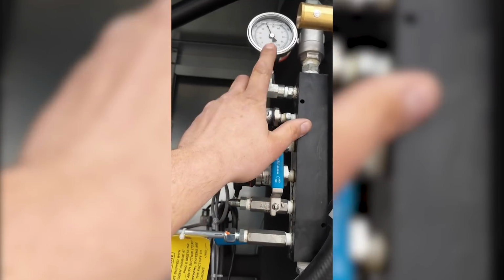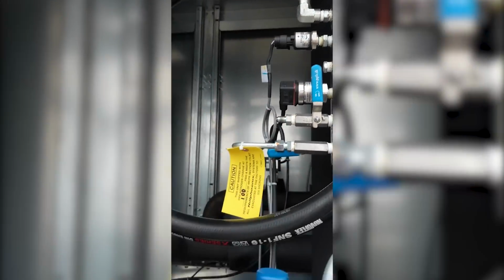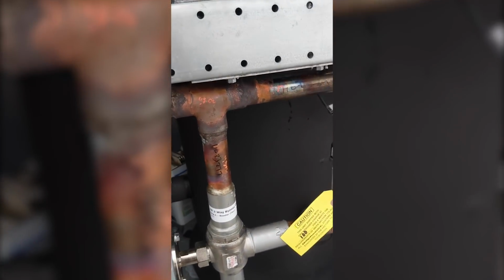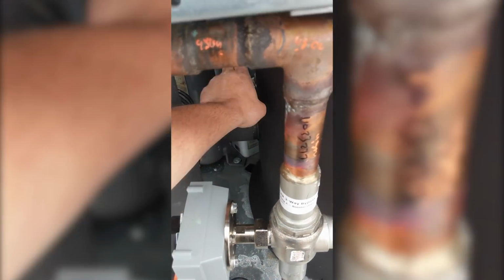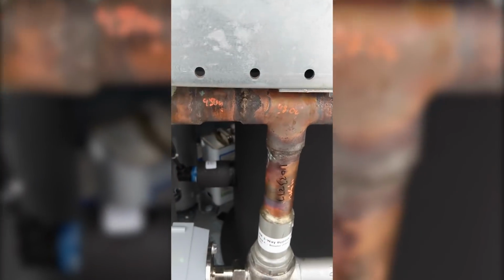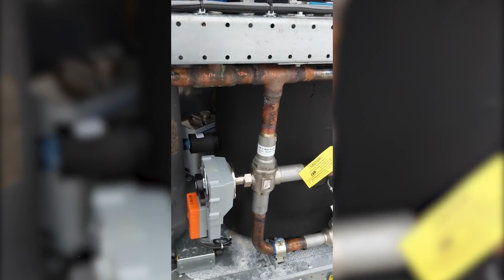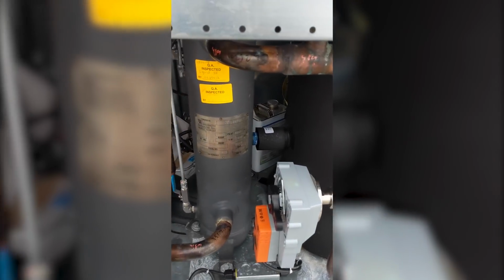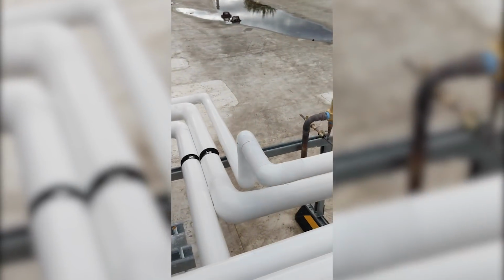You just constantly got to watch your vessel pressure up here just to make sure you're not going to hit your relief, and make sure both your compressors are going. It has to be over the low liquid level indicator. I like to see between 1 and 2 balls floating. I mean, it's a little more CO2 than you need, but that way if it gets colder, you don't have any issues. You just want to be careful and make sure you don't pull the reliefs.